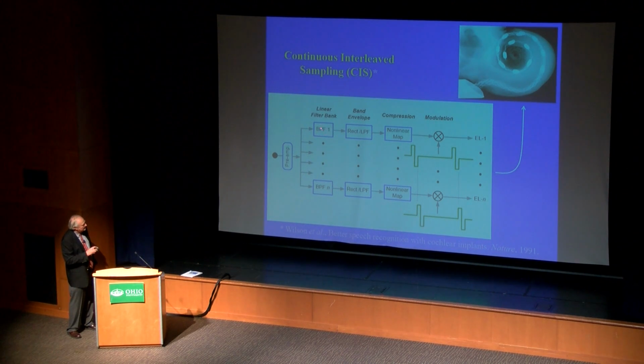And then for each frequency range, detect the energy in that range of frequencies. And the simplest way to do that, as engineers know, is with a rectifier followed by a low-pass filter. There are many other ways to do it, but that's the simplest and it works well. So the low-pass filter controls the maximum frequency variations that are transmitted to the recipient of the cochlear implant ultimately. And that low-pass filter typically is set at 300 hertz or 400 hertz, corresponding to that limit that I mentioned to you before for perception of different frequencies of stimulation at a single site.